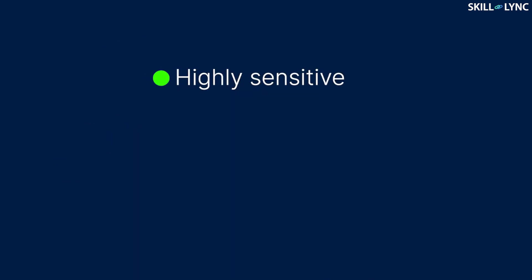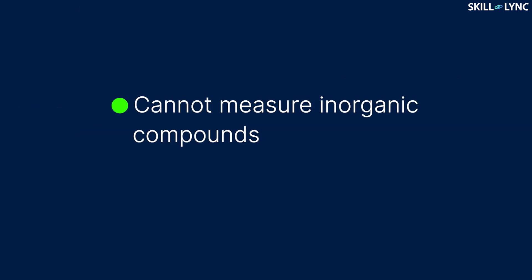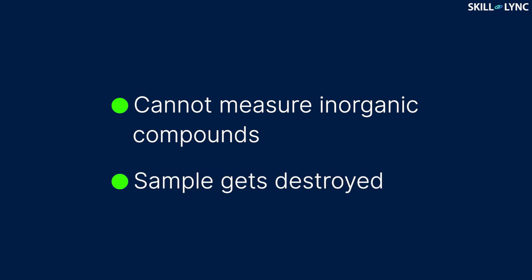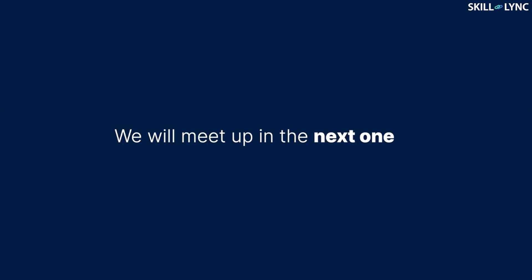This analyzer is highly sensitive, rapid, accurate, and can be used continuously. But it cannot be used for measuring inorganic compounds in the exhaust, and the sample is destroyed in this test. That's all about the flame ionization detector. Stay tuned for more interesting videos.